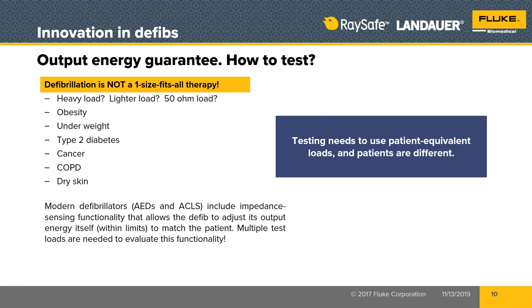Okay. All right. So there is also, as we look at these automatic external defibrillators, and at the newest, say in the last 5 years or so, maybe a little longer, full advanced cardiac life support defibrillators, we see the ability for them to have a little bit of an output energy guarantee. Now, what do I mean by that? That means that for any defibrillator, the energy level that it is charging up to, whether set by a dial setting by the doctor or the nurse, or whether it's an AED and it automatically has a setting that it's supposed to deliver, that value should be what's delivered to the patient at the paddles or the pads.